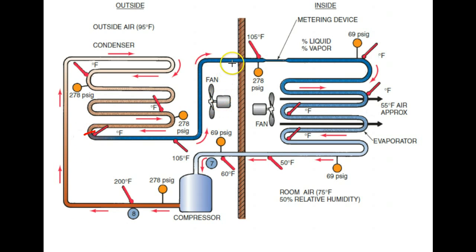Once again, if it sheds 10 degrees between here and here because it's backed up, and we have less refrigerant, that backup point doesn't happen until here. And then that decreases our amount of time that the refrigerant spends in the condensing coil and it decreases the subcooling level of the refrigerant. So you've hooked up your gauges. You find out you have five degrees of subcooling when you should have 10. You know that your refrigerant isn't backed up in the condensing coil like it should to shed that extra five degrees. So you're going to begin adding refrigerant to the system.